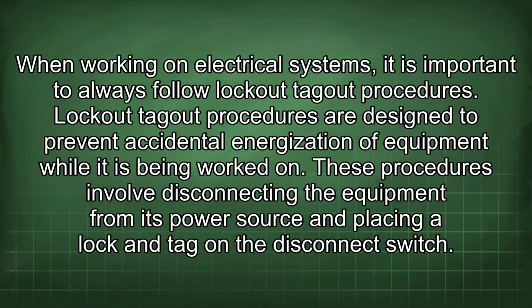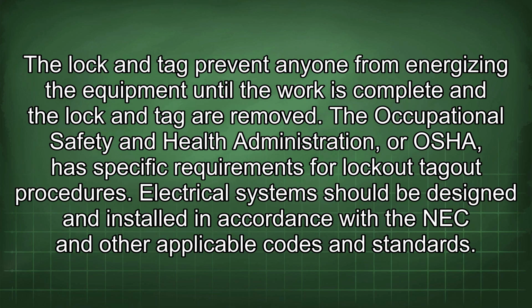When working on electrical systems, it is important to always follow lockout-tagout procedures. Lockout-tagout procedures are designed to prevent accidental energization of equipment while it is being worked on. These procedures involve disconnecting the equipment from its power source and placing a lock and tag on the disconnect switch. The lock and tag prevent anyone from energizing the equipment until the work is complete and the lock and tag are removed. The Occupational Safety and Health Administration, or OSHA, has specific requirements for lockout-tagout procedures.